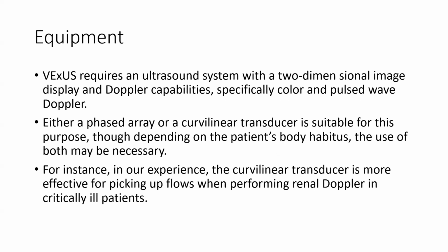Now about equipment. VExUS requires an ultrasound system with two-dimensional image display and Doppler capability, specifically color and pulse wave Doppler. Either a phased array or curvilinear transducer is suited for this purpose, though depending on the patient's body habitus, the use of both may be necessary. For instance, in our experience, the curvilinear transducer is more effective for picking up flows when performing renal Doppler in the critically ill patient.